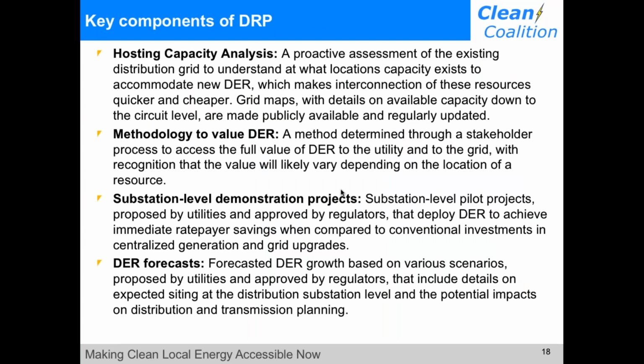The first is hosting capacity analysis. This is a proactive assessment of the existing distribution grid to understand at what locations capacity exists to accommodate new DER, which makes interconnection of these resources quicker and cheaper. Grid maps with details on the available hosting capacity down to the circuit level are then made publicly available and regularly updated.